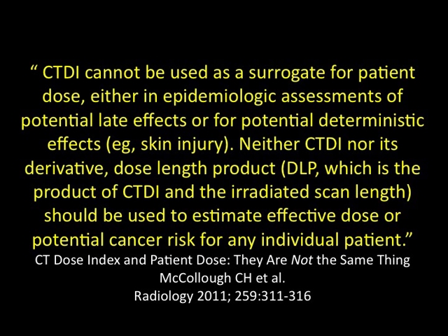be very careful that CTDI cannot be used as a surrogate for patient dose, either in epidemiologic assessments of potential late effects or for potential deterministic effects short-term, like skin injury. Neither CTDI nor its derivative dose length product should be used to estimate effective dose or potential risk for any individual patient. Very, very important.